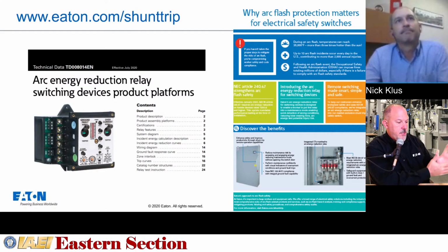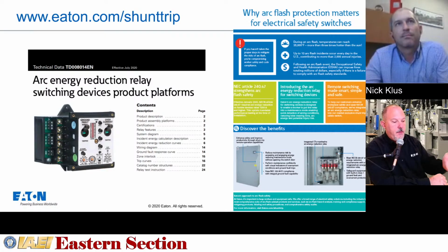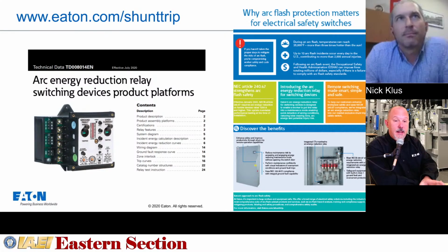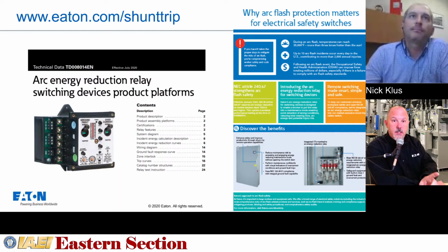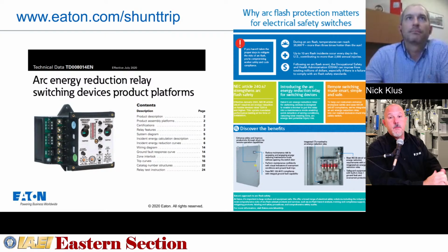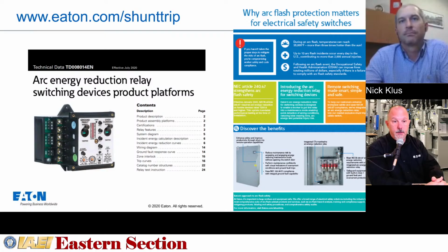Awesome. Well, Nick, we got a couple questions for you. Bill Shell is asking, do all of your safety switches have the required PPE level applied on the outside of the cabinets? We'll take that one first. Remember, Bill, PPE level is determined based upon available fault current, arcing currents, and a systems analysis study. Nick is a smart dude, and he's got a lot of other smart dudes working with him. But we can't label that equipment before it leaves the factory with a personal protective equipment level, because based on IEEE 1584, you're required to rely upon the upstream overcurrent device that's feeding that equipment. We don't know what that is, and we don't know what the fault currents are. So we can't put the PPE level on the outside.